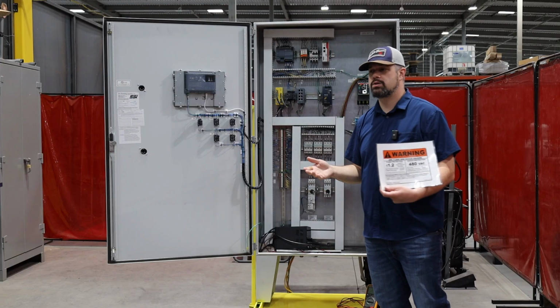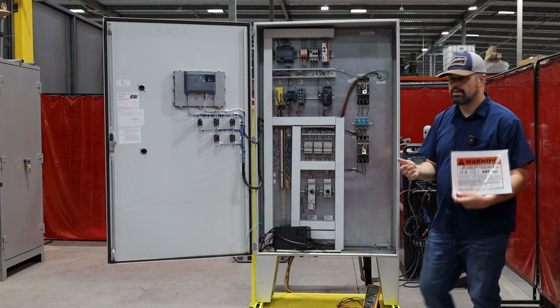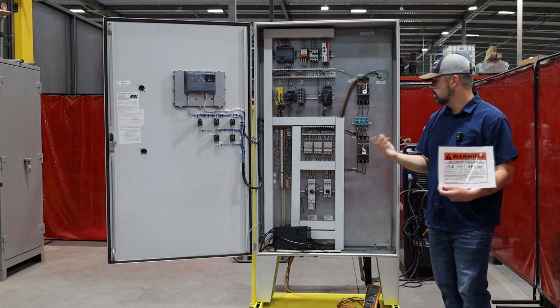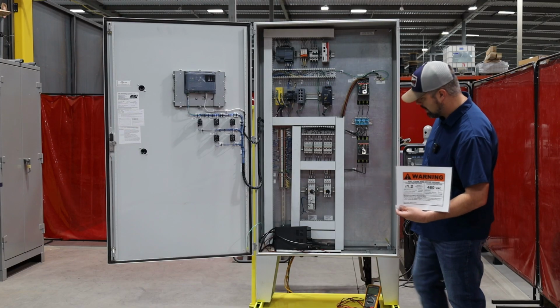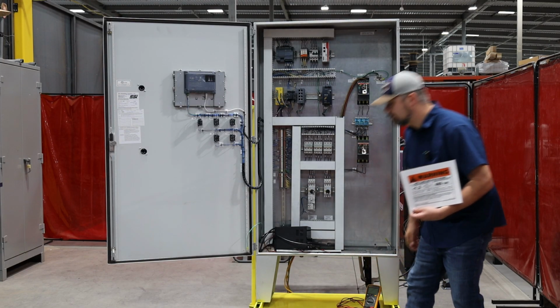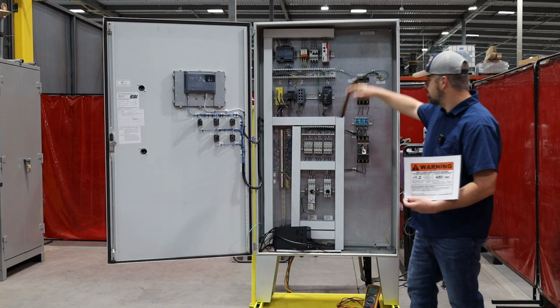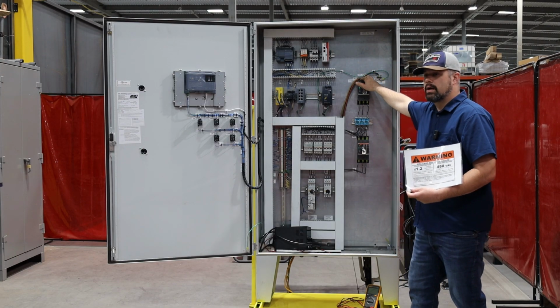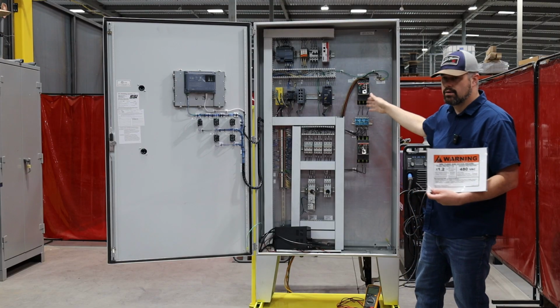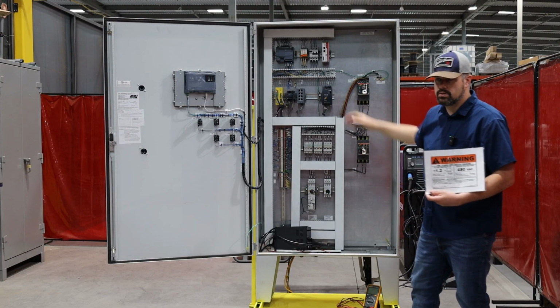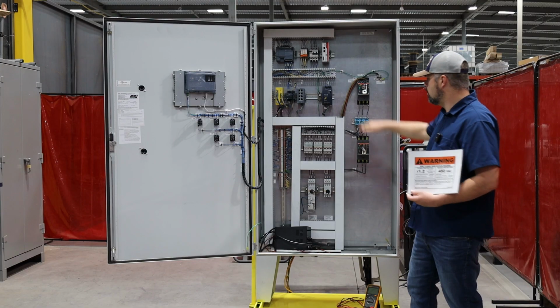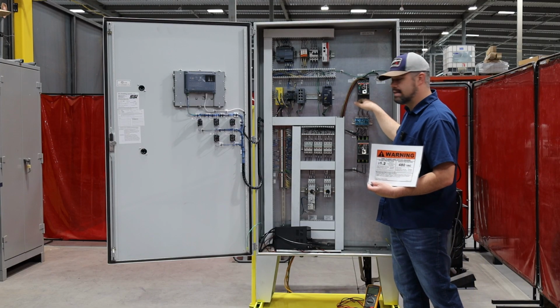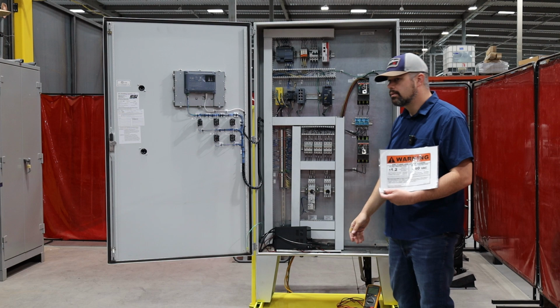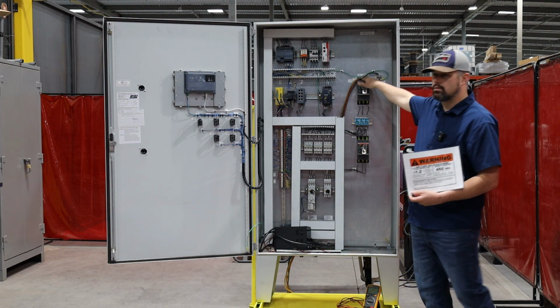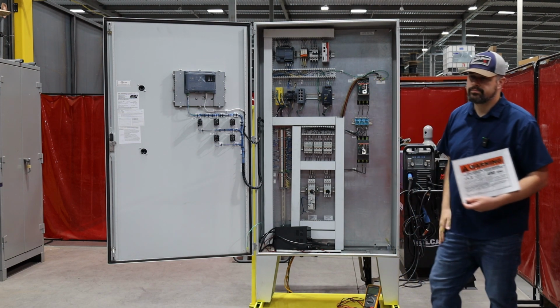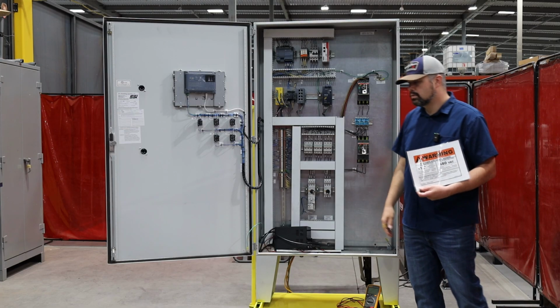probably one of the most important parts of verifying an electrically safe working condition is identifying all sources of power. Step 1. Okay, so we've got power coming into this cabinet. Not on this cabinet, obviously, it's a training aid, but if we had power coming into this cabinet, it's coming in on the top side, right? So if we throw this disconnect and we visually verify it and we use our meter to make sure there's no volts, it's all well and good, and that kills power to everything downstream of this disconnect, everything in this panel, but you still have voltage present right here, right?